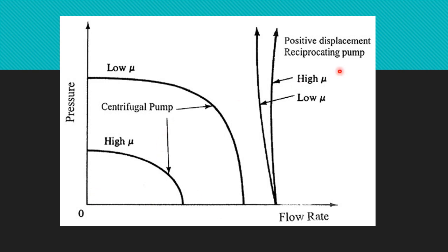Centrifugal pumps need priming whereas reciprocating pumps do not. The efficiency of centrifugal pumps is less compared to reciprocating. Centrifugal pumps can handle dirty water and all types of fluids, whereas reciprocating pumps cannot handle dirty or viscous fluids, and they produce more noise. This is the pressure and flow rate curve of a centrifugal pump and a positive displacement pump: in centrifugal pumps, as flow rate increases the pressure decreases, whereas in positive displacement pumps the flow rate remains constant regardless of pressure.